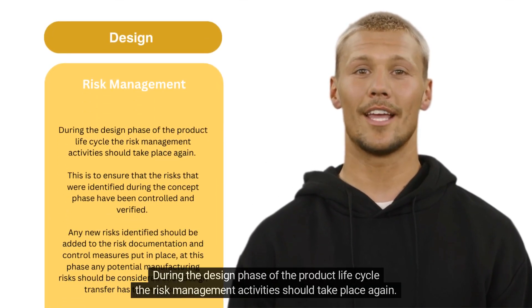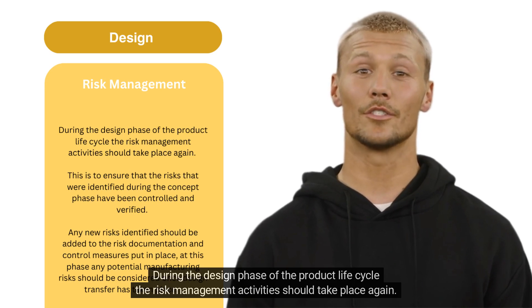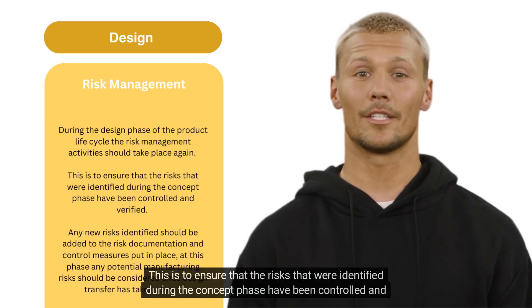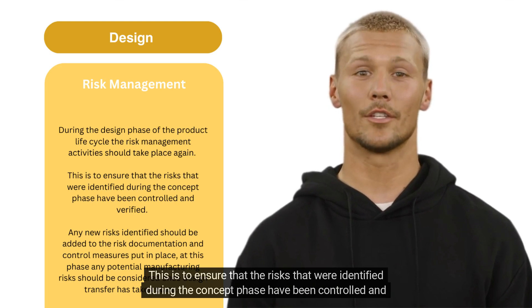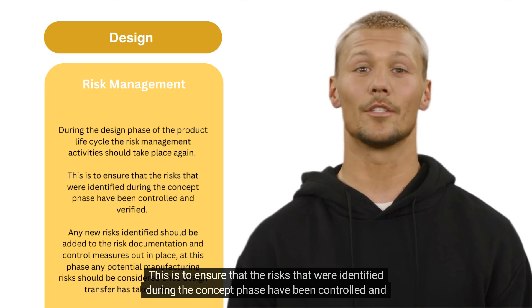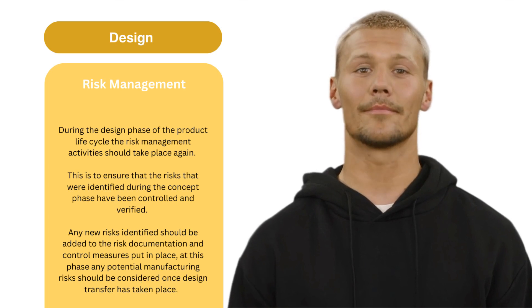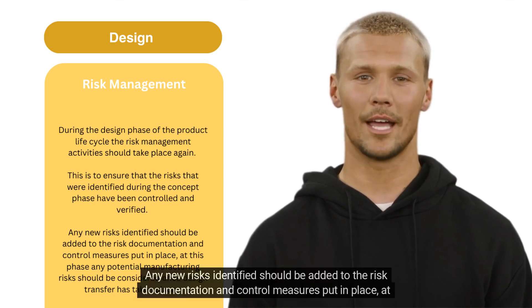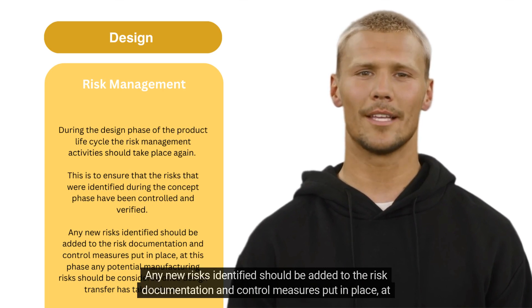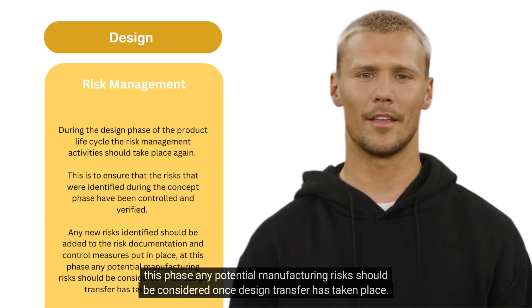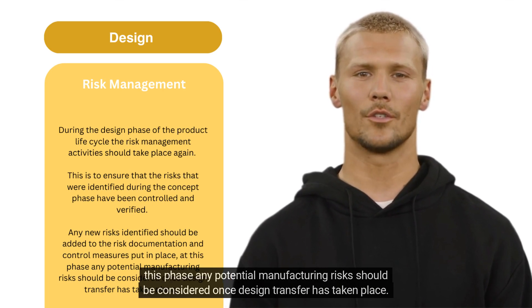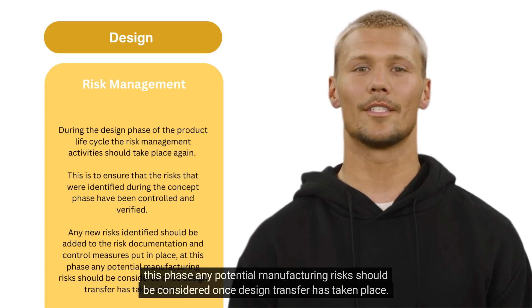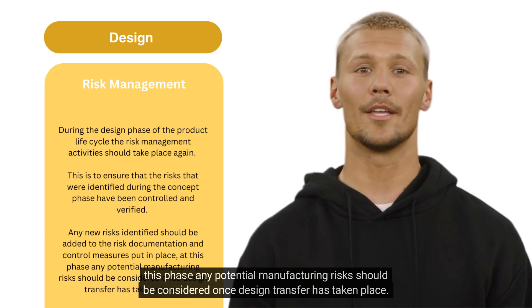During the design phase of the product life cycle, the risk management activities should take place again. This is to ensure that the risks identified during the concept phase have been controlled and verified. Any new risks identified should be added to the risk documentation and control measures put in place. At this phase, any potential manufacturing risks should be considered once design transfer has taken place.